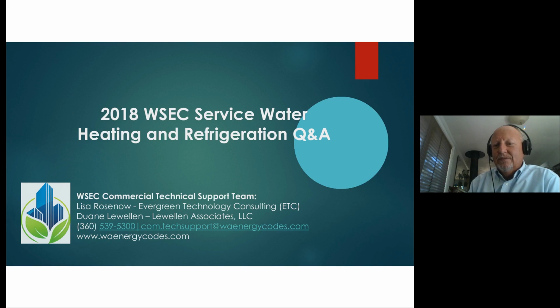CHP allows us to reduce the demand on the traditional water heater by as much as 100%, depending on electrical demand on the generator. Yeah, I do not believe combined heat and power, assuming that it's a fossil fuel source, is renewable energy. However, it is energy recovery or heat recovery, because you're generating electricity, I assume, and then you're recovering the exhaust from that process heat to serve a heating demand, whether that's service water heating, heating the swimming pool, or heating the building. So I wouldn't consider it renewable. I would consider it energy recovery, though.